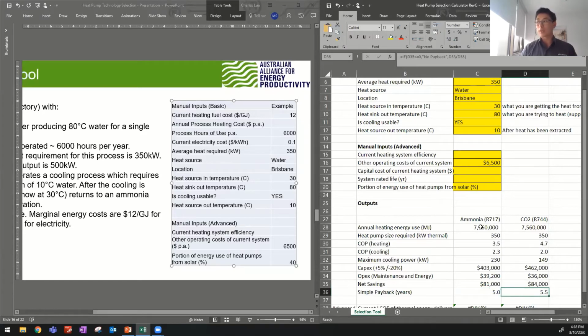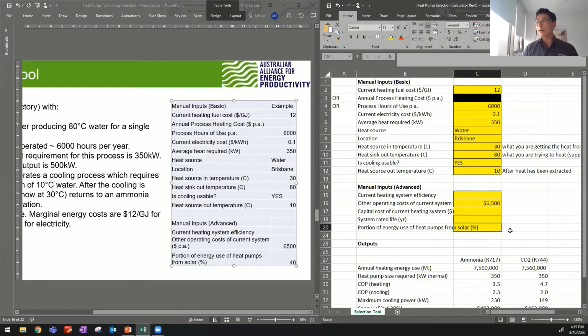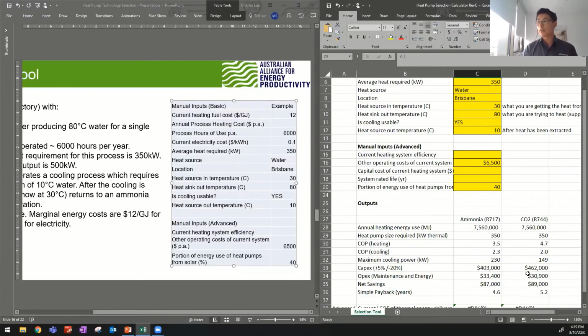Looking at this tool, you'll probably look at ammonia as a start because it's got fairly low CapEx and good savings. CO2 can do the job as well. It's fairly close and the savings are similar, but the cost of CO2 systems is typically higher at the moment. And you can add to this the use of solar power. So if I say I'll have a PPA which supplies 40% of this heat pump's energy use with solar power, which is far cheaper than the site's current electricity cost, you can see the payback dropped from 5 years and 5.5 to 4.6 to 5.2. The whole purpose of this tool is just for you to play around with your figures. What works on your site? What's your current circumstances? And it gives you some rough numbers.